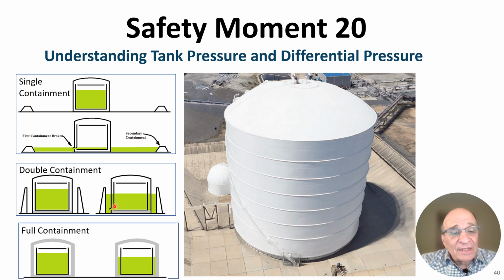So when your inner tank fails, the outer tank also fails, but the LNG is contained in this close encounter or close proximity outer dike. And what you do is you'll have vapor leaving, but the liquid will be fully contained. Up in the single containment tank, you have a tremendous amount of vapor leaving because you have a high surface area that's in contact with the LNG. And in the double containment tank, you have a much smaller surface area.